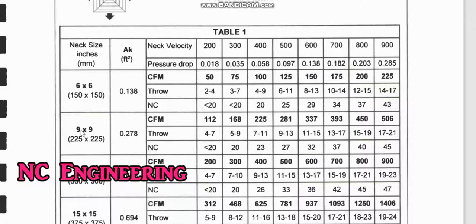We can only go up to NC 30, so the 6x6 is not applicable. Let us go for the next size: 9 by 9 inch. For 225 CFM, the velocity is 400, which is less than 600, and the NC level is 23. So we will select the diffuser of size 9 by 9 inch for the CFM of 225.